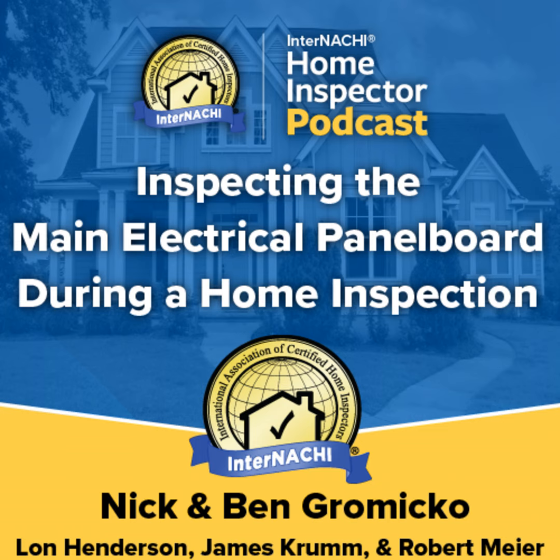Grounding electrode conductor, or GEC. The GEC is a conductor that connects the system grounded conductor or the equipment to a grounding electrode or to a point on the grounding electrode system. The GEC is copper, aluminum, or copper-clad aluminum. It is not intended to carry current except in case of a ground fault. It can be bare and without color. The GEC is usually connected to the grounded service conductor, or neutral service conductor, in the service equipment where the main disconnect is located or in the meter enclosure.